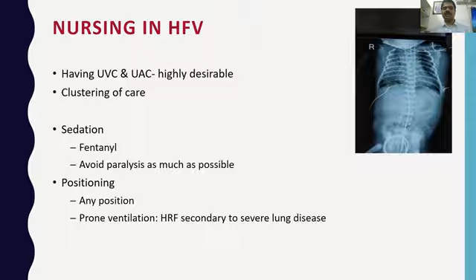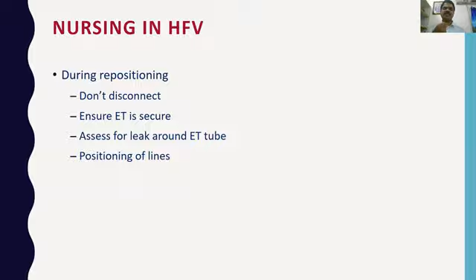The other important thing is repositioning. Usually you tell the staff to change the position of the baby every 6 hours like that, for routine conventional ventilation. So you should give baby-oriented directions to the nurses, whether that repositioning is required or not. If the nurse is doing repositioning, don't disconnect the circuit and ensure the ET is secure. And once the staff repositions the baby, assess for the leak around the endotracheal tube, and again check for the positioning of the lines.